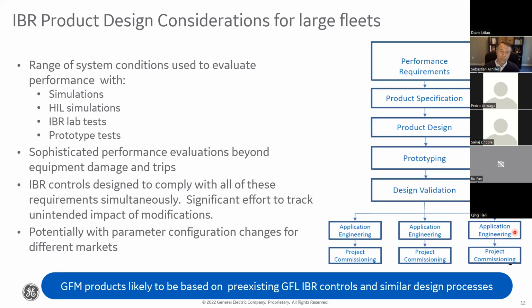So in a way, as we're seeing, you take a product that is grid following and modify its controls to add grid forming features. By doing this, you may create unintended consequences for other things that were working, which you then have to address. But fundamentally, you try to reuse as many of the features already created for grid following as possible, for aspects that don't contradict the grid forming features. I think that's an important consideration.